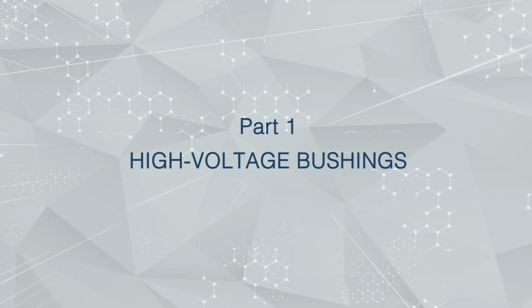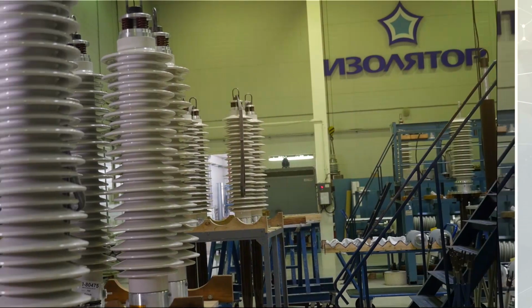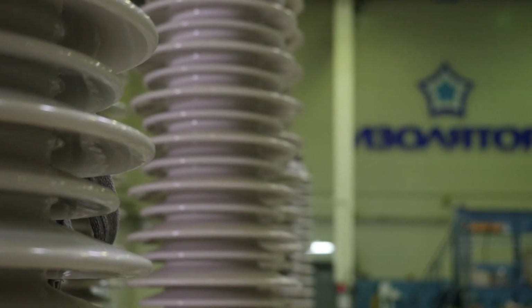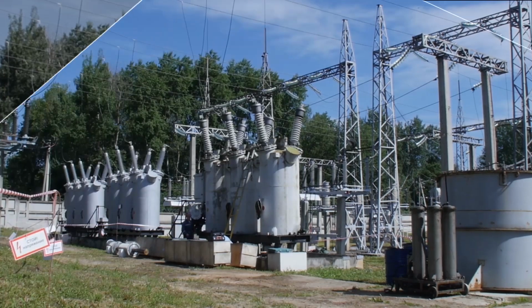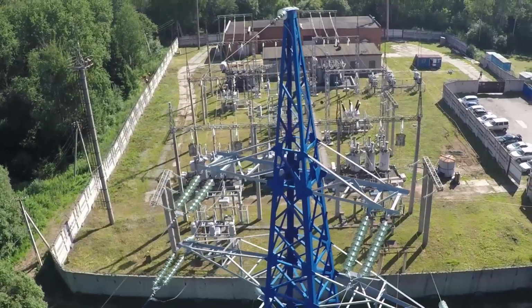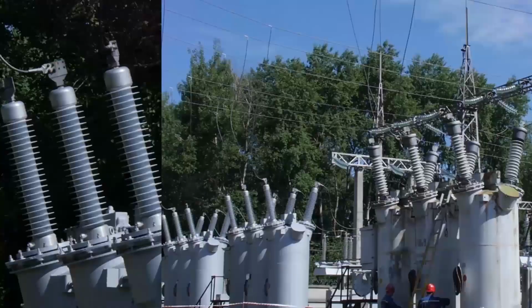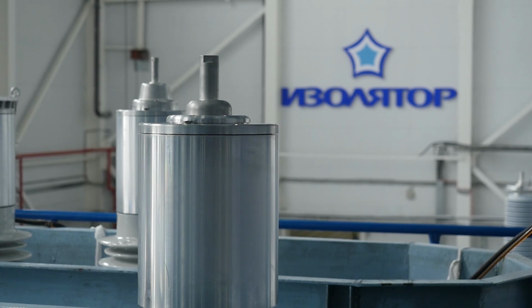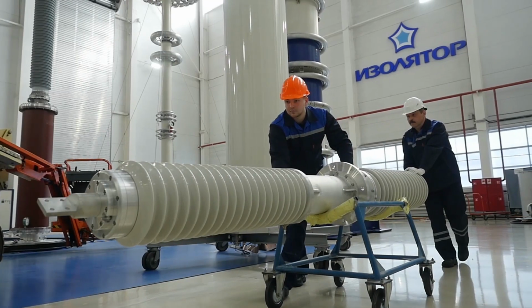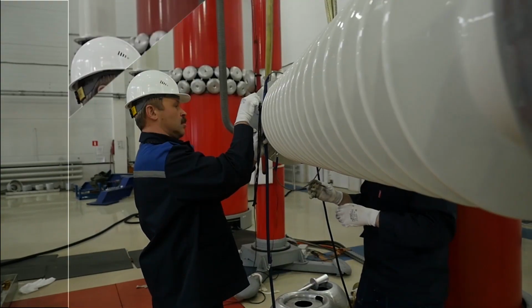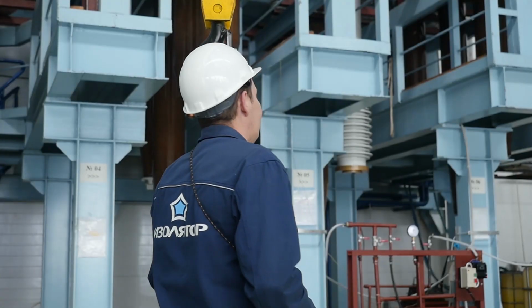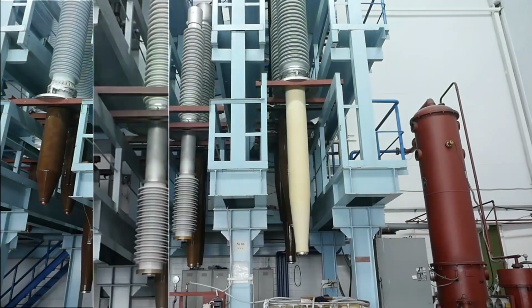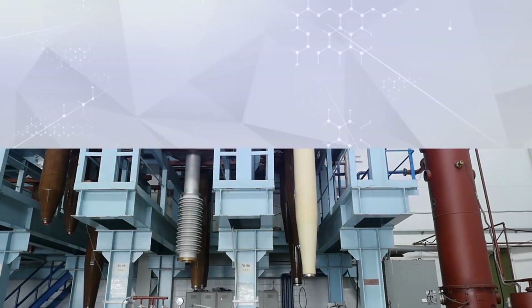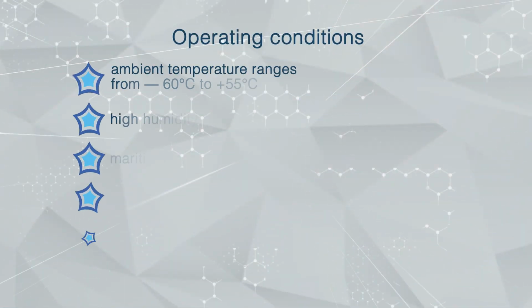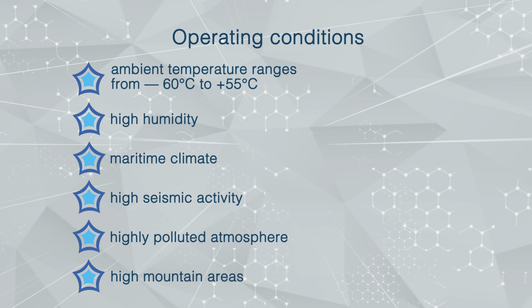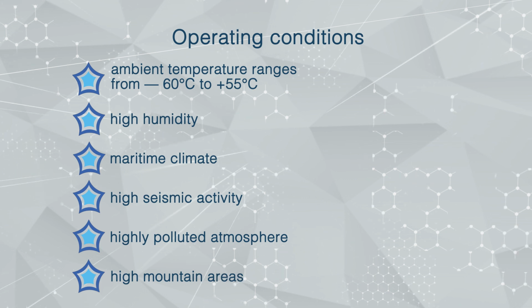High-voltage bushings. High-voltage bushings are the most important link between an electrical transmission line and other electric equipment. For an uninterruptible and quality operation, bushings are created to meet the design features of such equipment as transformers, shunt reactors, oil circuit breakers, gas-insulated switchgear. The external and internal insulation of a high-voltage bushing provides a reliable and stable power supply even in the most adverse conditions of the operating environment.